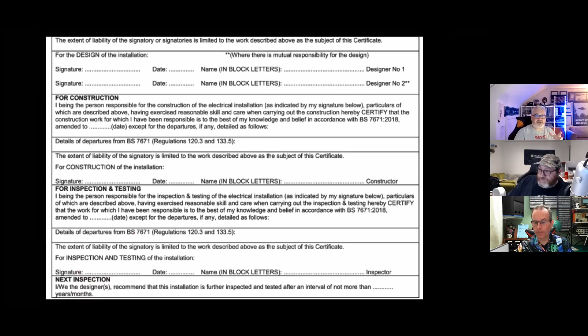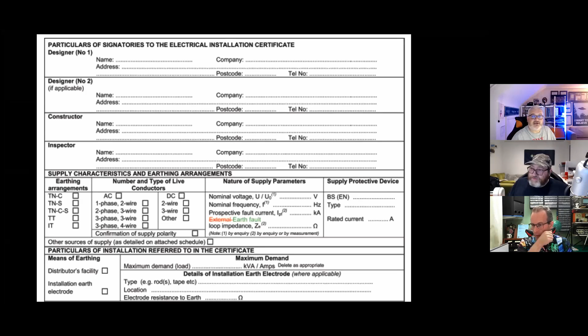Particulars of signatory, one key change on the signatory page where it says external earth loop impedance - they've deleted 'external' and now put 'earth fault loop impedance'. Really? Seriously, come on guys. So we're not testing Ze anymore now? It's a supply parameter, but hang on - it says Ze, which means Ze external symbol. What genius, how much money did these people get paid to sit in that meeting and come up with that one? Is this standardized? Is that the problem, is that why that's happened? Is that happening in 60364? We should check that, might be. We should check it, let's look at 60364-6, we'll have a look and let you know.